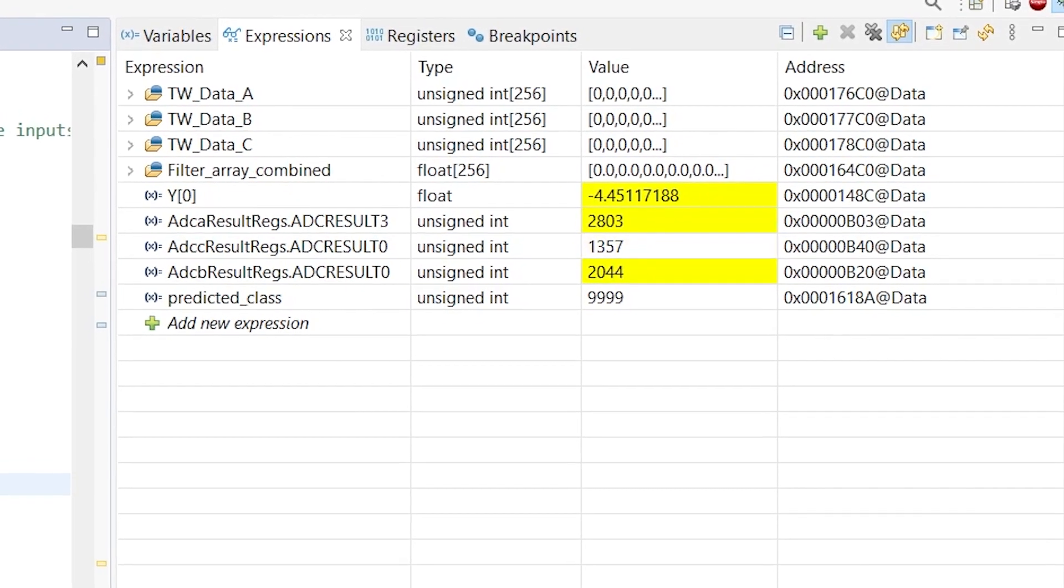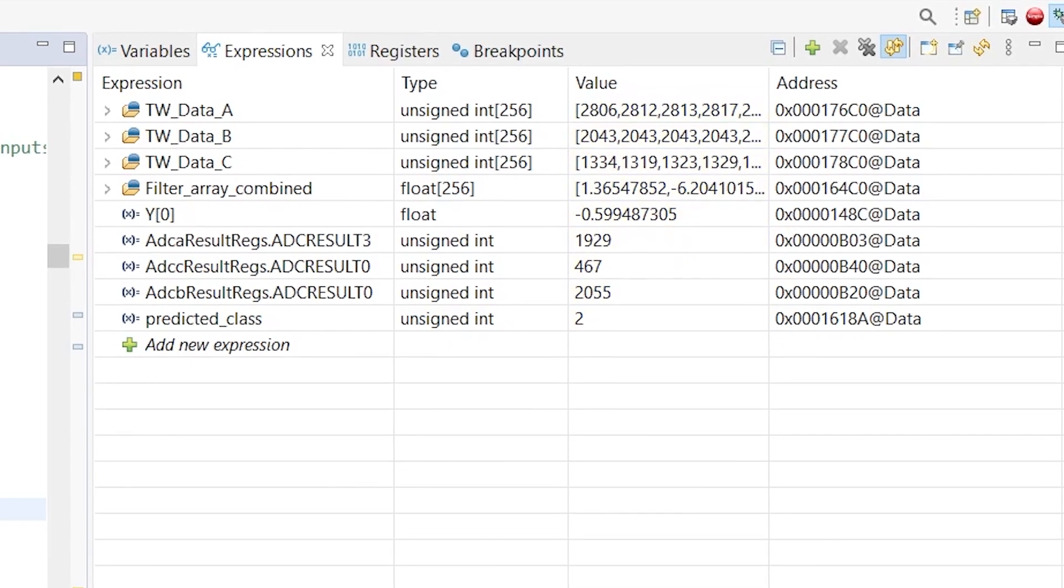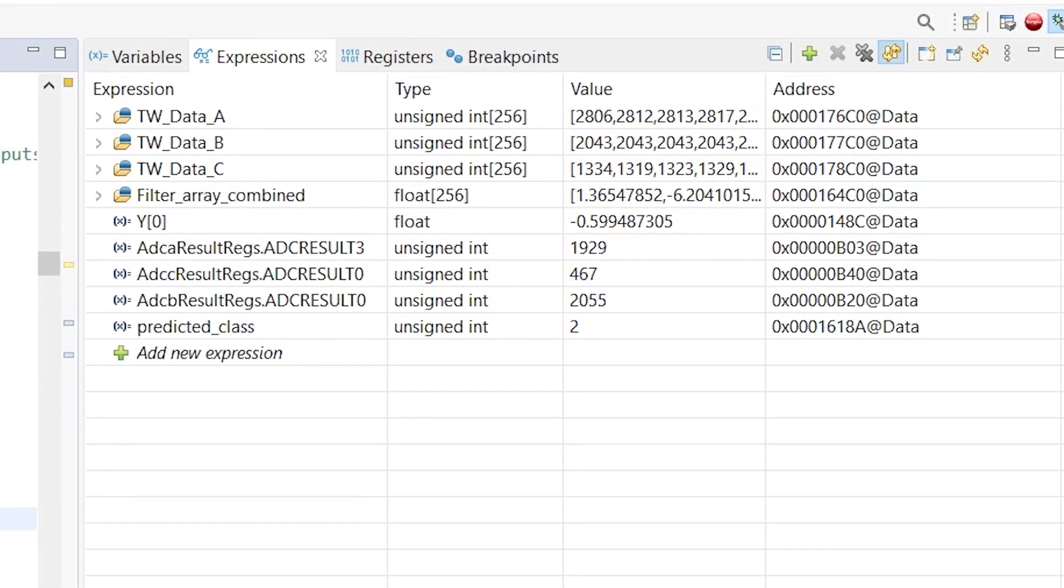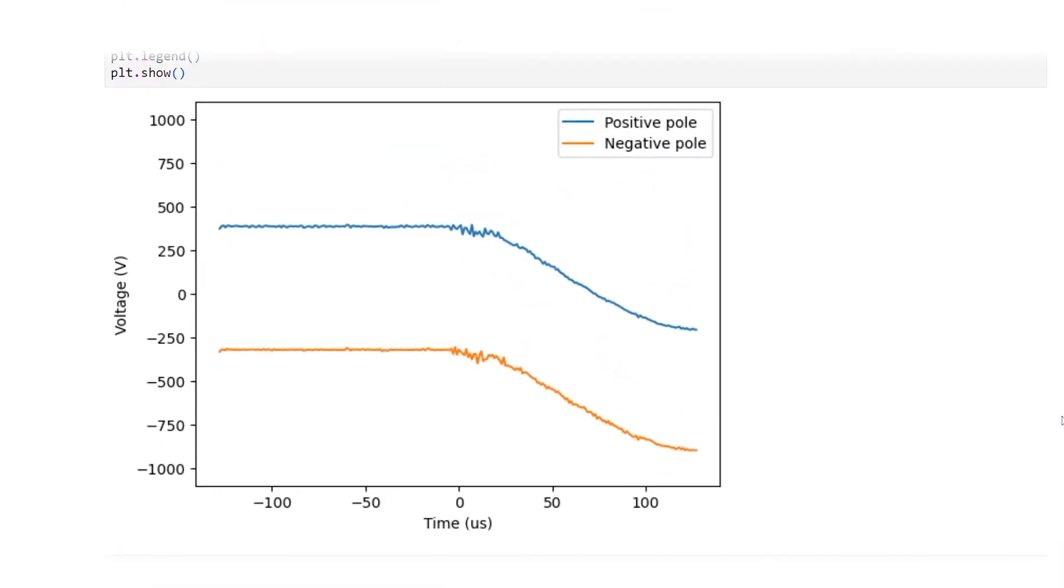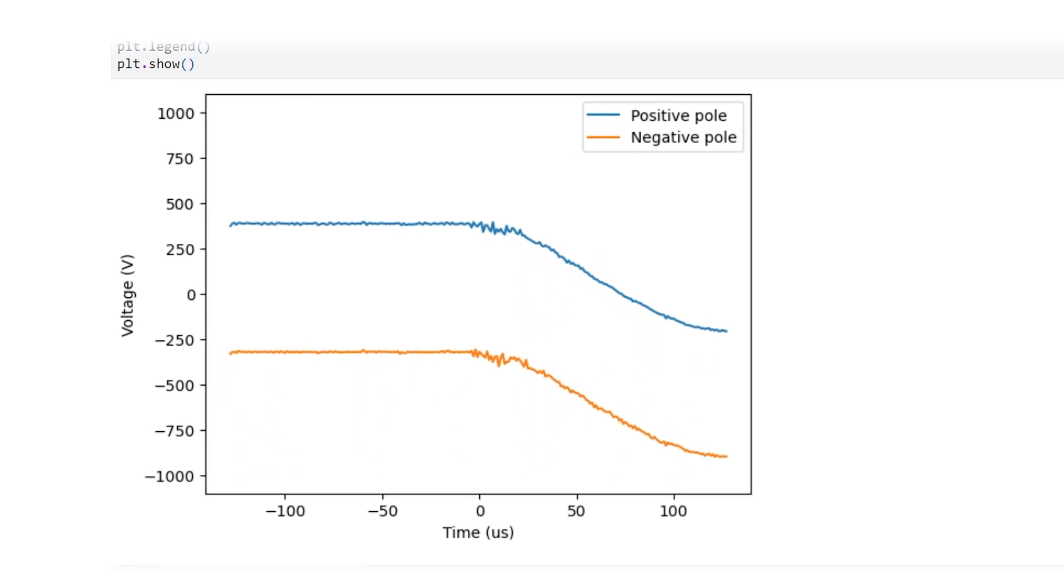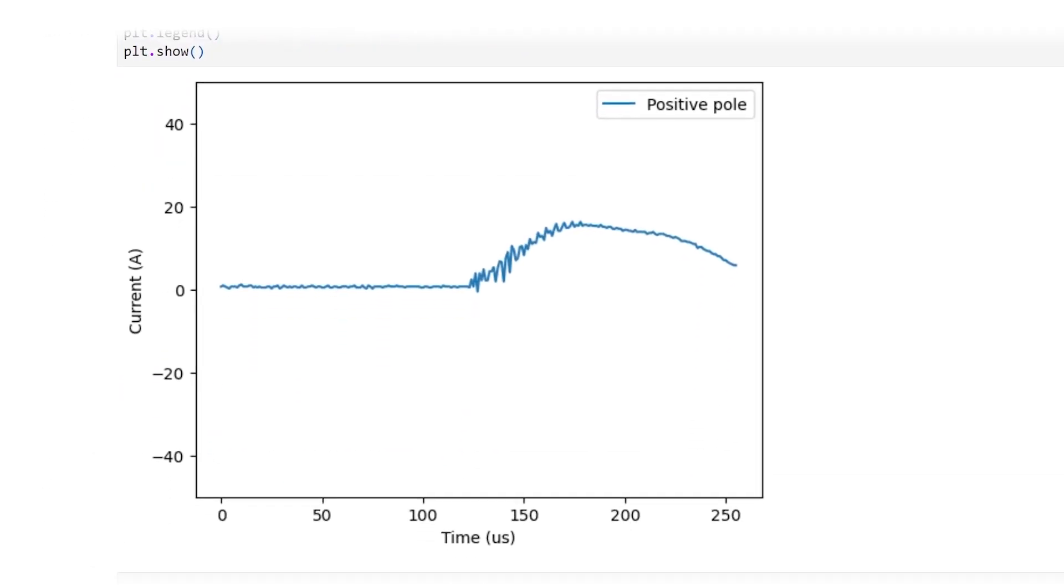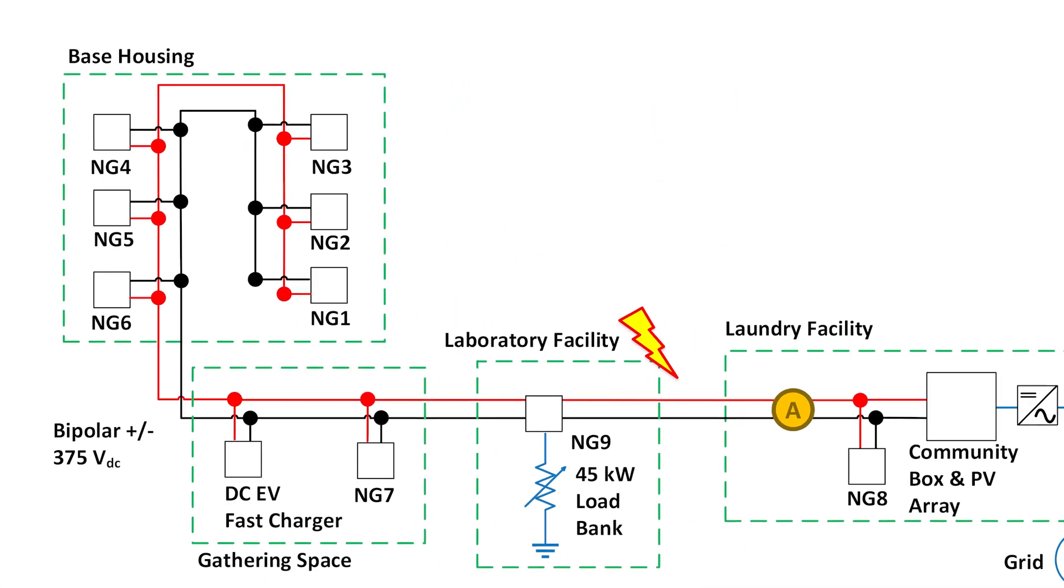As mentioned before, the relay triggers on the traveling wave in about two microseconds when a fault occurs. Data around the trigger time is captured and sent to the laptop through serial communication. Our algorithm is able to determine the location of the fault and display that to the user.